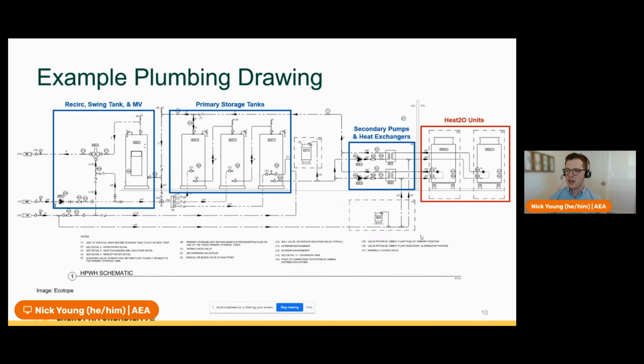One thing you may notice is that on our recirc return here, in addition to going into the swing tank, we also have a manifold here to send the recirc return back to the primary storage tanks. One thing we're doing with this project at a few demonstration sites is actually testing the viability or feasibility of returning the recirc return to the main storage tanks.